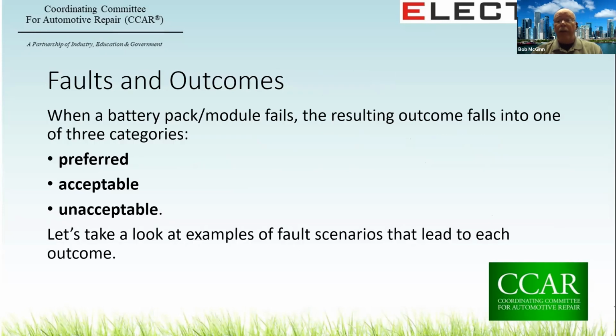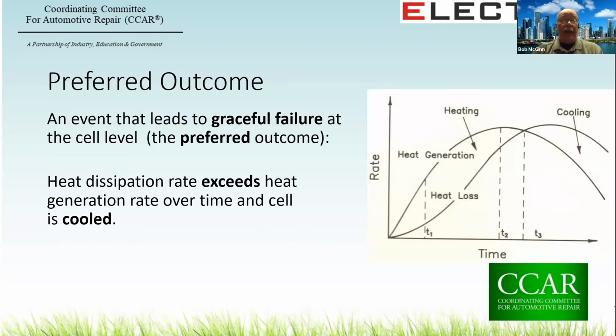So when a battery pack module fails, the resulting outcomes fall into one of three categories: preferred, acceptable, or unacceptable. So let's have a quick look at each of the fault scenarios and what outcome they lead to. First up is a preferred outcome, a graceful failure. If you're looking at the plot on the screen now, you'll notice that the heating rate and the cooling rate, as plotted, there's no numbers on it, they just trend at approximately the same rate.